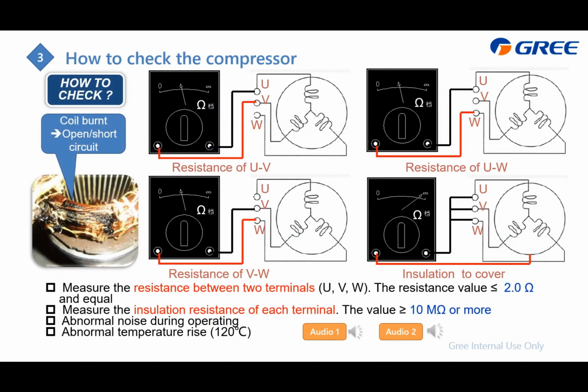And for the compressor malfunction, we're just afraid that maybe the inside coil, just like this picture, will just burn, and also lead to the inside open. This is the wire, for example, this is the UVW. This wire is open circuit or short circuit. So we just need to check the resistance value of this coil.